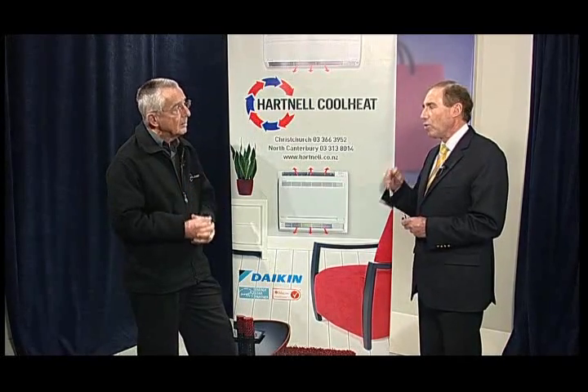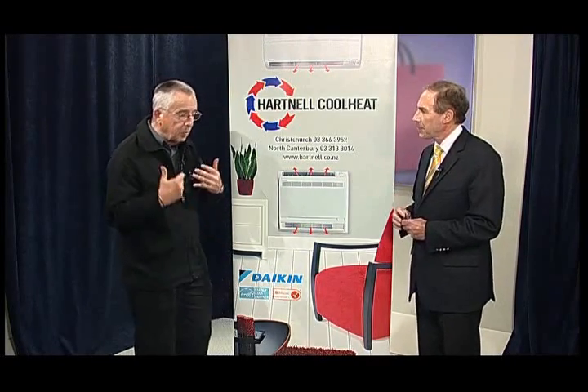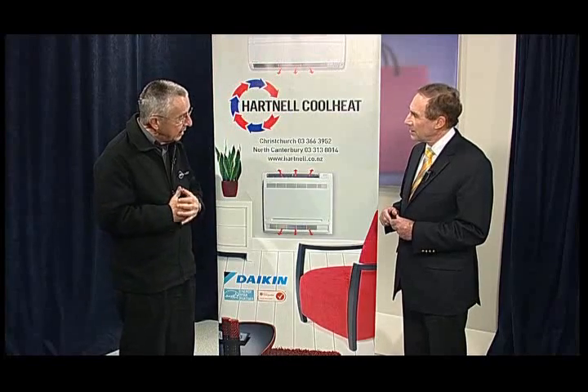Now, what is the process? Once you've arrived, what do you then carry out? When I do a call to people's houses, the first thing I say, and it's a catchphrase, is, Mike, what's on your wish list? Because it's really important for me to listen to what the client's expectations are. Once I've got that, then we can start. Obviously, we do the drawing, we do the calculations, which tells us how many kilowatts we want. Then we make the choice between the high wall or the floor unit.